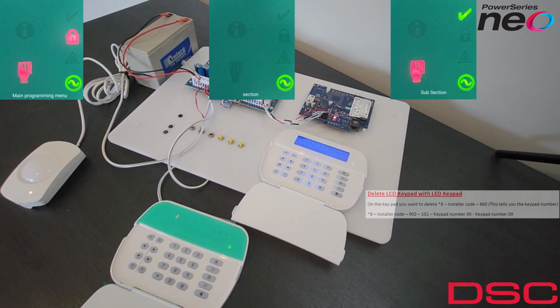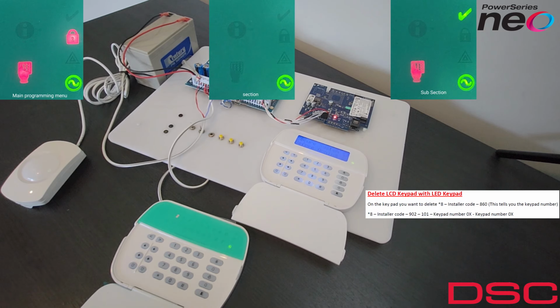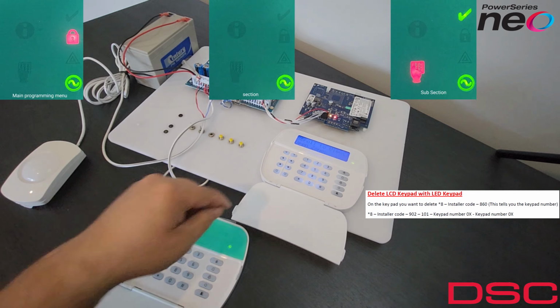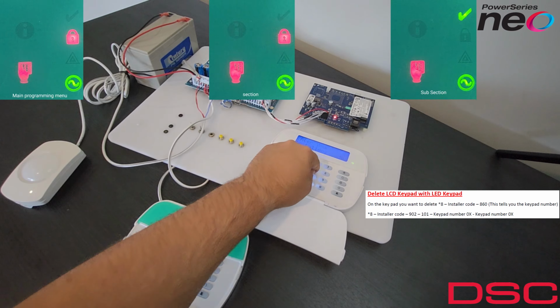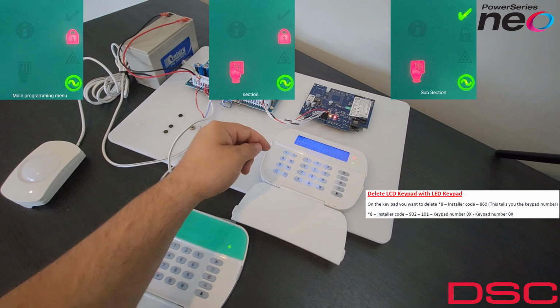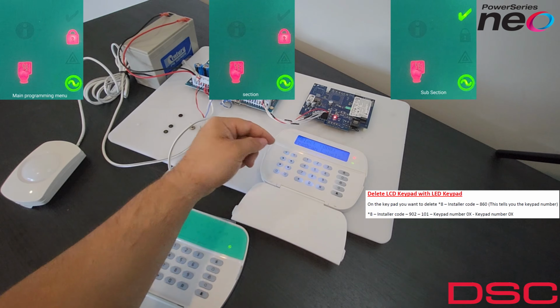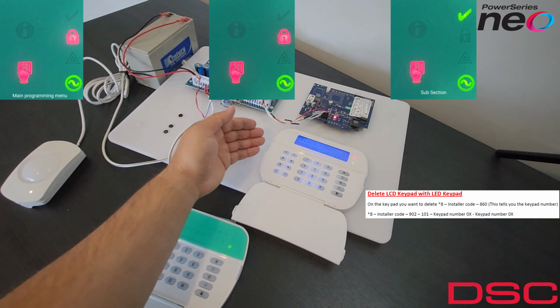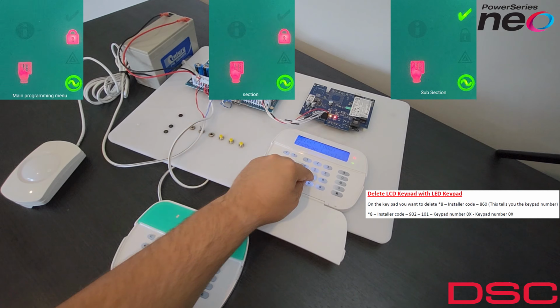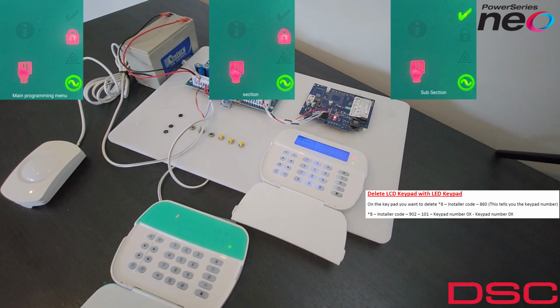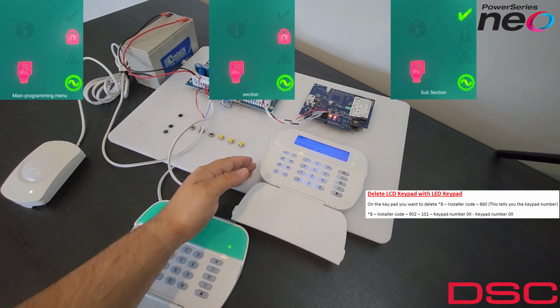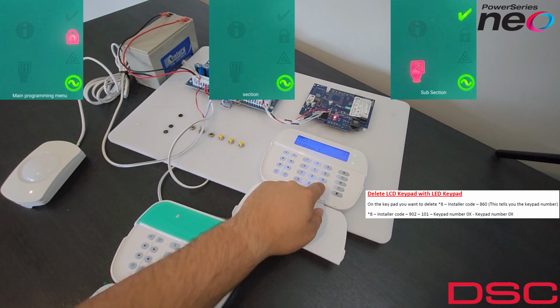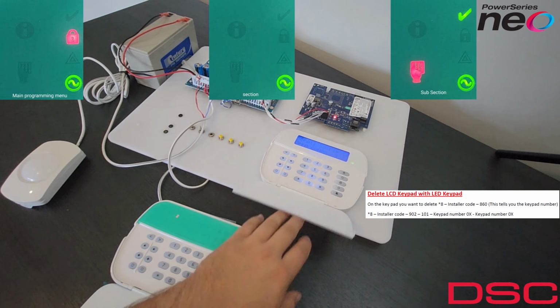Okay, so last part of this video is if you went through and programmed everything with an LCD keypad, you're going to want to know how to delete it. So we're going to go *8 5555 for your installer's code, and then we want to check what keypad the LCD keypad is. So for that, just go 860. Now you know it's keypad number 1. So we just hash all the way out of programming here.